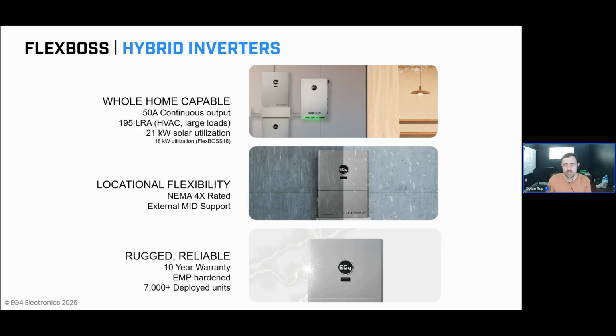Now, certainly that is the average home, so you are going to have some subset of homes that are using more than that 40 amps of continuous usage during their high energy demand moments. And where those come across, the FlexBOSS can easily be paralleled and scaled to deliver reliable power capability for those homes as well. And what you're going to find is paralleling two of these inverters with a 100 amp continuous output is going to be able to meet the highest energy use moments for 98% or more of homes in the US. So this unit is more than power capable to reliably back up customers, even if they choose not to change their behaviors in the context of an off-grid moment in time. They will also have that reliable power to fully offset any consumption from the utility using only the power that's available within their energy storage system.